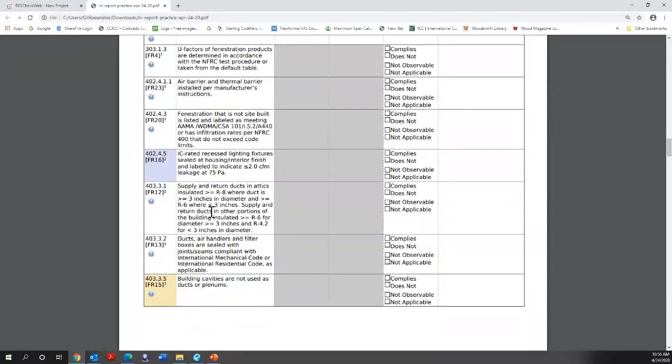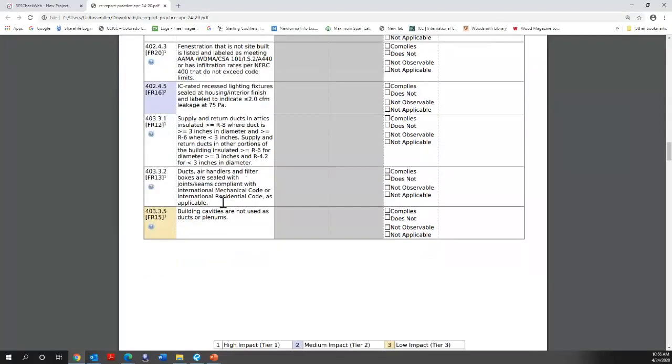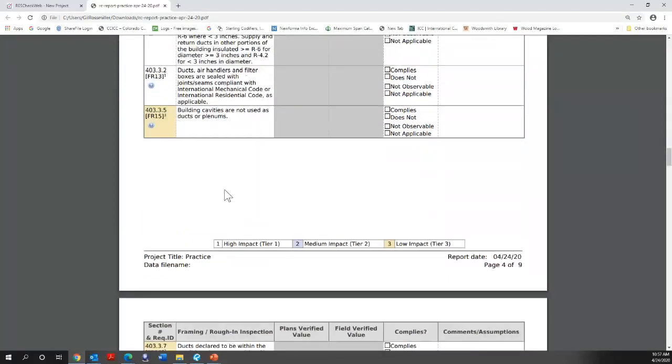You've got insulated ductwork. Oh my goodness! Even insulated ductwork in the attic. When it's in the attic and it's an R8, it can add a ton of air conditioning load easily, even if it's insulated to that R8. So that's a big deal. If they're in the attic or an unconditioned space, they need to be insulated because they're already a drain on the system. Sealing ductwork and things of that nature.